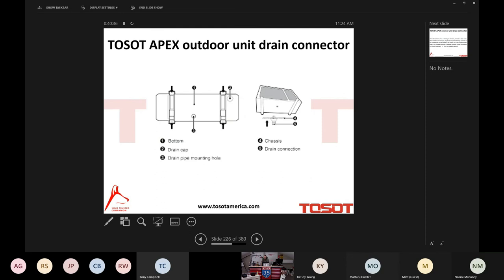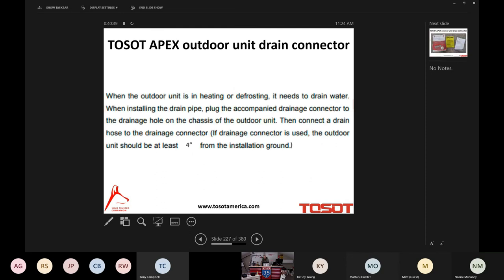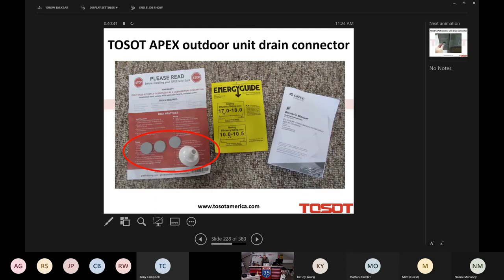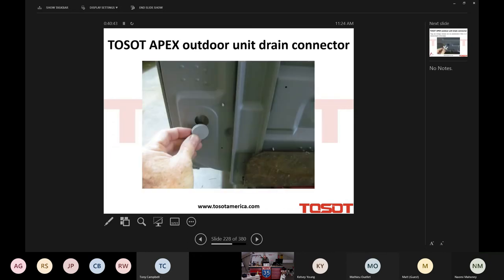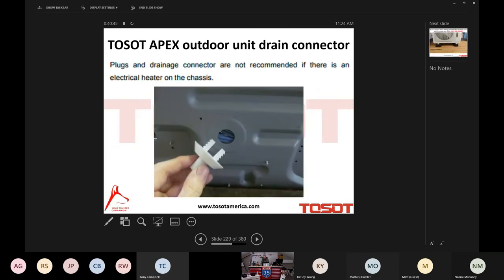The drain connector, again, I'm going to go back to that and just show it to you in action. There it is. Comes in the goodie bag of the outdoor unit. We're going to plug up all the existing holes, put it in that singular hole. I just want to point out that in that hole, when you first look at it, crossing over it, internal to the outdoor unit, is the heating element of the base pan. Not a problem. You can literally move it out of the way with your finger and insert that fitting if you choose to use it.